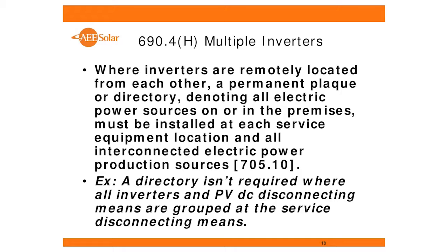The way the 2014 code is written currently, if we've got multiple inverters in multiple places, we do use placarding at each place that they're connected. So we have a building like this. We could have several sub-panels that have different PV systems connected to them. We're not required to bring them all to one location. But at each location where we have connections made, we have to have placarding, and it has to essentially show where the other locations are. So we don't want to go crazy with putting 2 inverters on every sub-panel in a building when you've got 20 sub-panels. But if they are in different places, then they would have to be placarded as such.